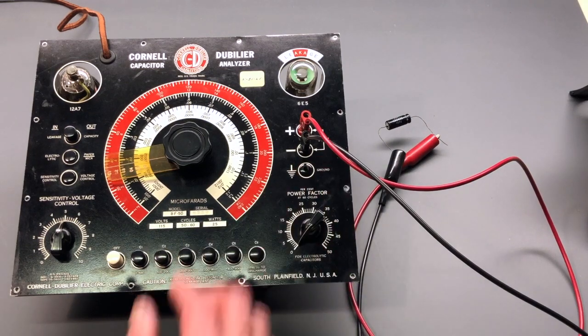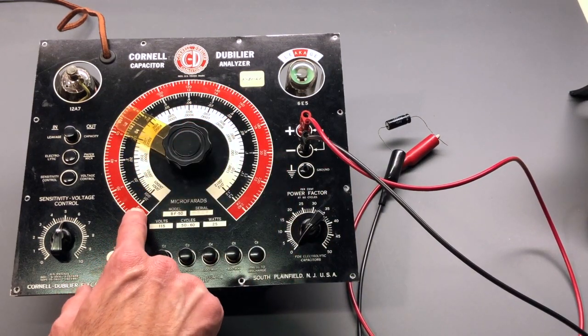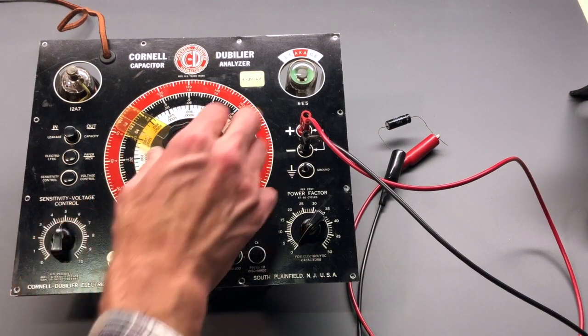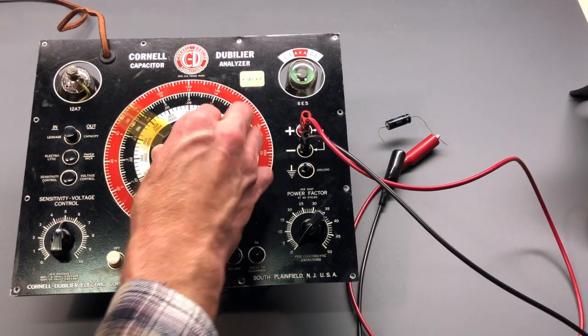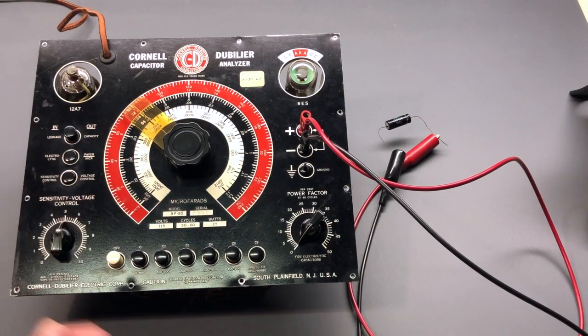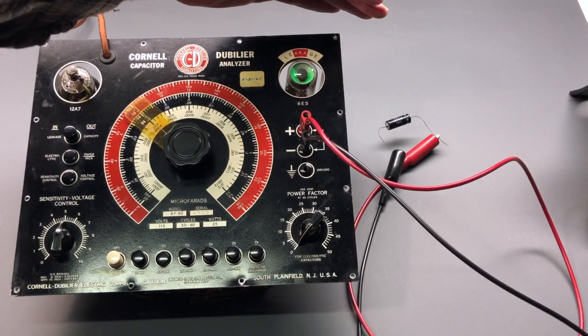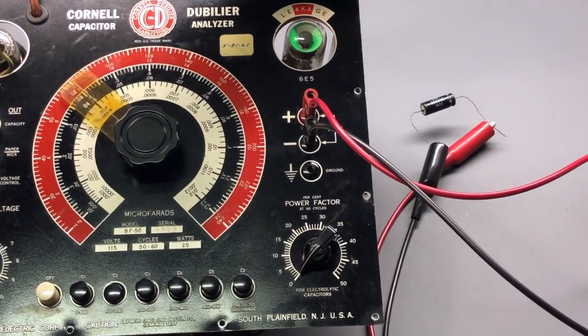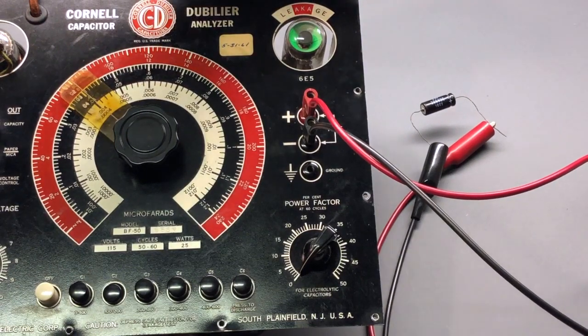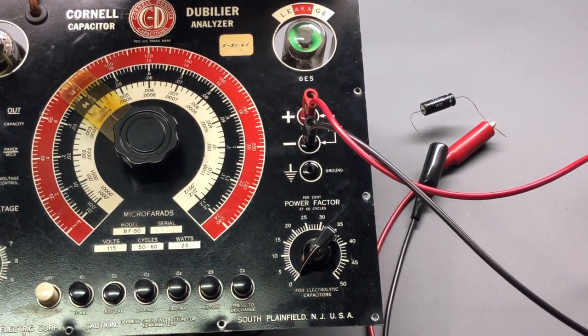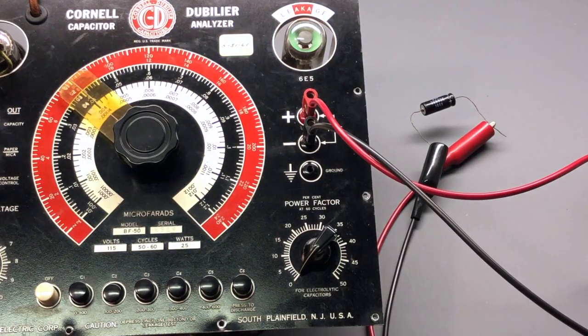So a very usable range, a very nice range that they built into this tester. This being a 3 microfarad capacitor, we can see that this second scale starts at 0.2, then goes to 2 and to 4. So of course right in this range here would be 3. And that is the C2 scale, or the second scale. So I'll go ahead and press that now. So the eye tube, let me zoom back in so you can see a little bit closer, like so. So the eye tube is open, and what we want to see is a balance in the bridge circuit, and I'll explain in a little bit about how the bridge circuit actually functions and what that is, and we'll take a look at the schematic.